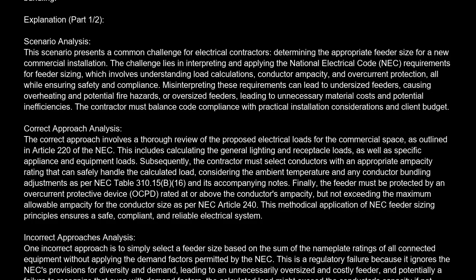outlined in Article 220 of the NEC. This includes calculating the general lighting and receptacle loads, as well as specific appliance and equipment loads. Subsequently, the contractor must select conductors with an appropriate ampacity rating that can safely handle the calculated load, considering the ambient temperature and any conductor bundling adjustments as per NEC Table 310.15(B)(16) and its accompanying notes.